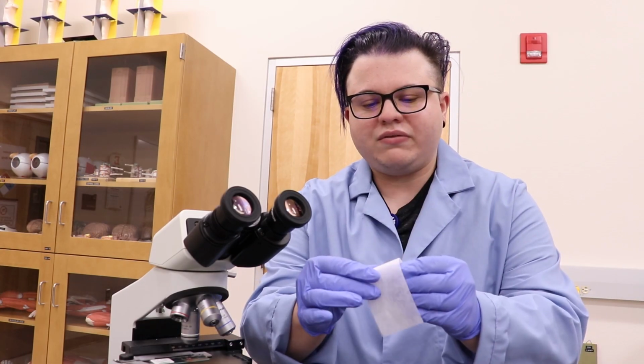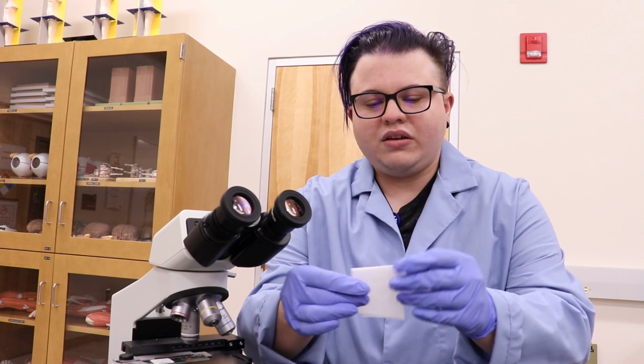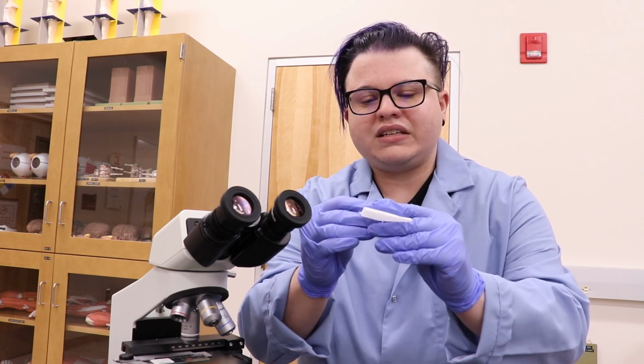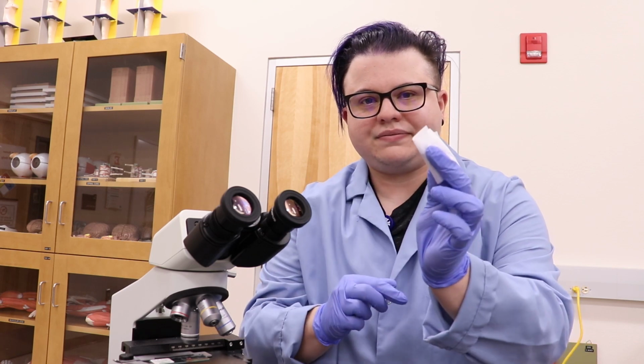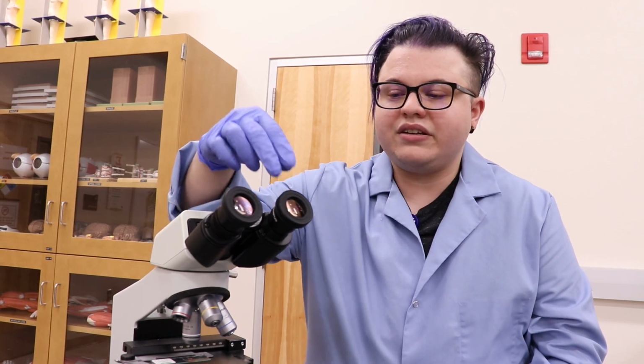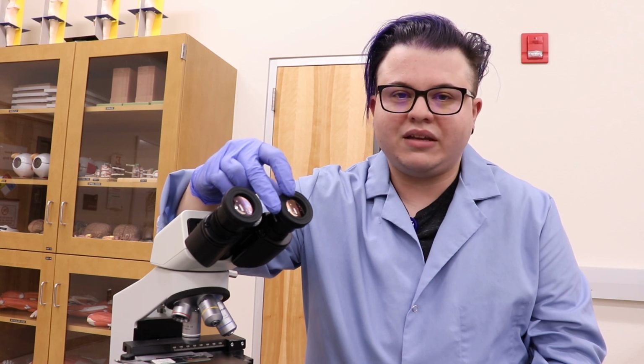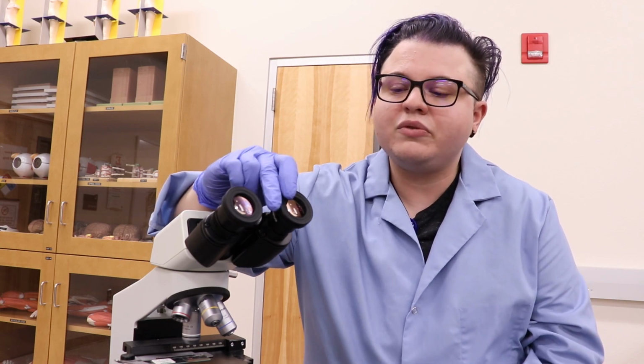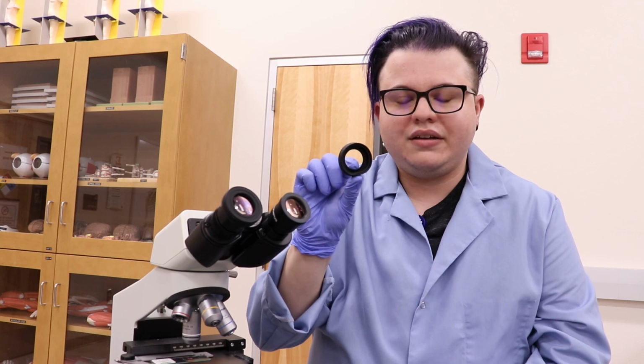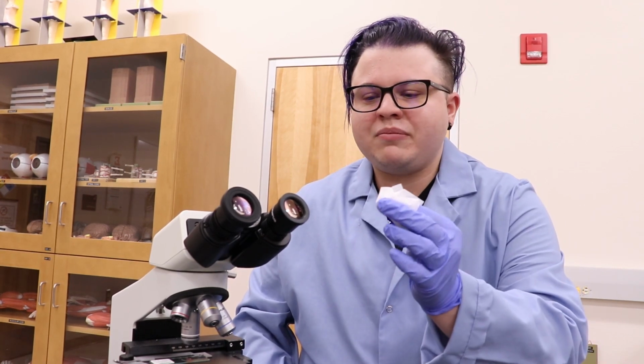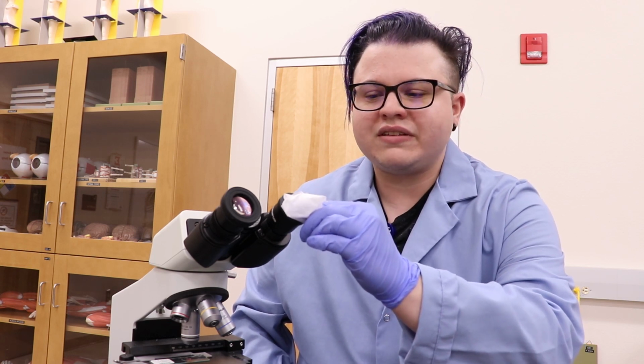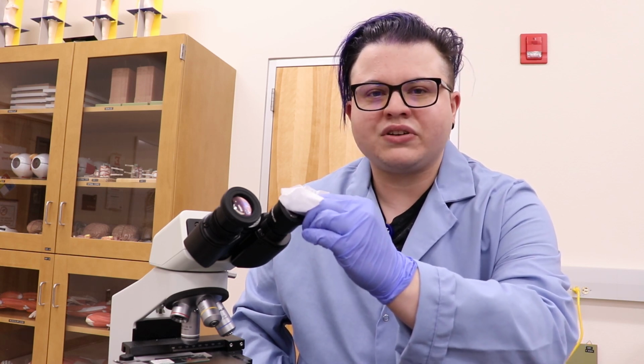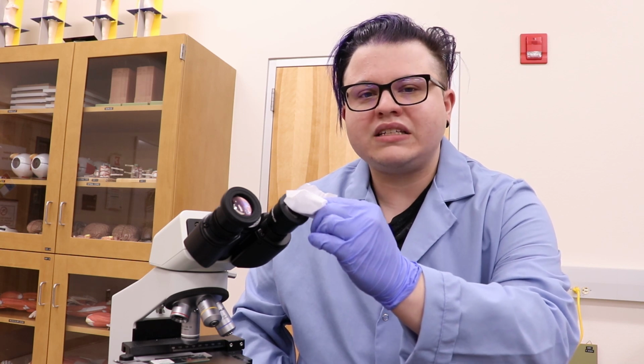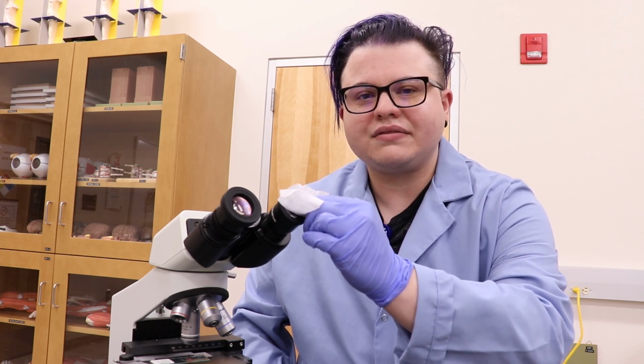To clean the eyepieces, we'll first take a piece of lens paper and fold it in half. And then you'll want to wrap it around your index finger and hold it in place like so. Cleaning the eyepiece might be made easier if you remove the rubber ring around the eyepiece if the microscope has it. So we'll be doing that here. To clean the eyepiece, you'll take the lens paper on your finger, gently touch it to the surface of the glass, and rotate in small circles. Continue doing this until the eyepiece glass is clear.